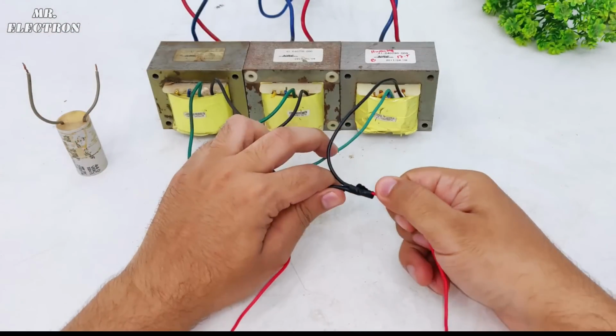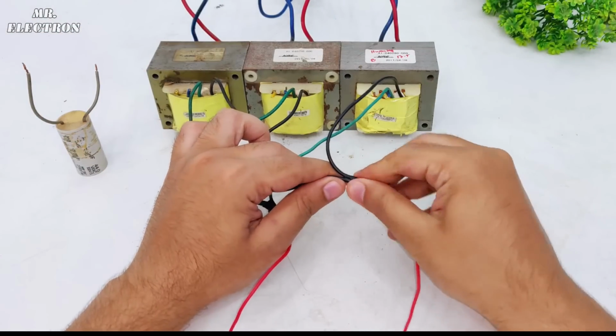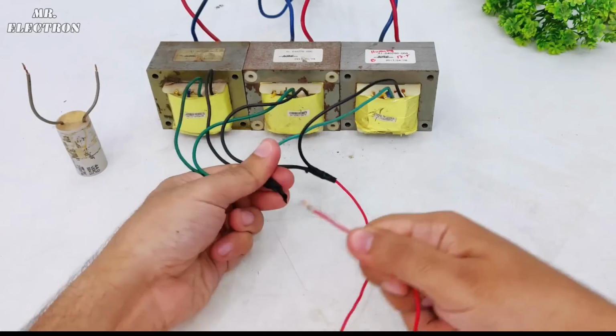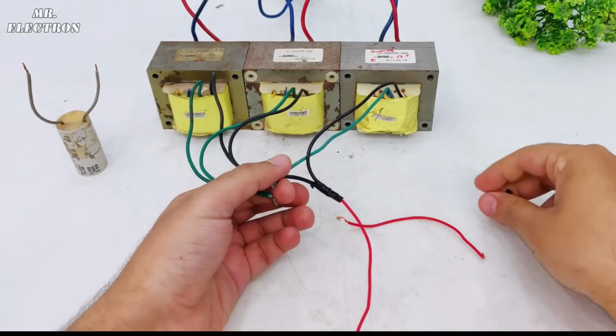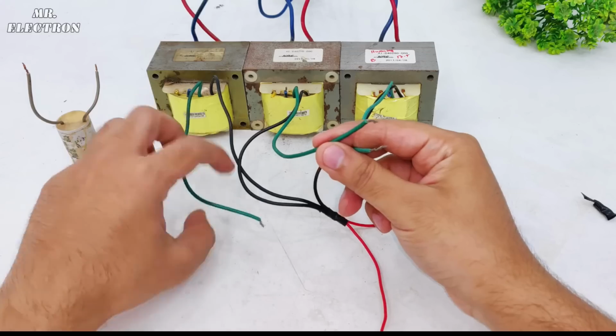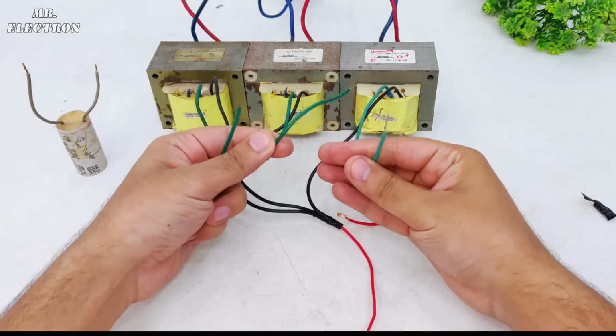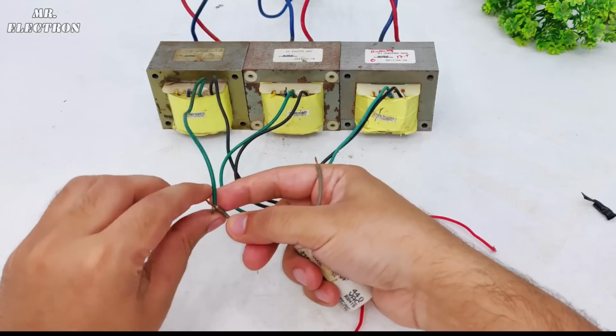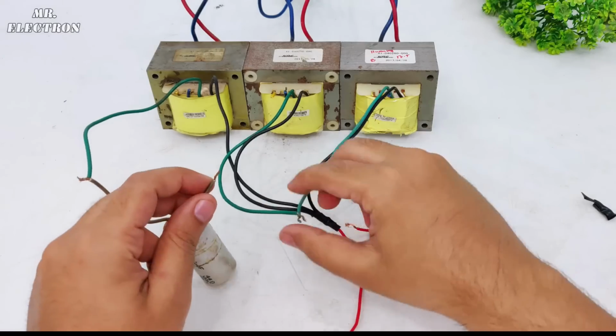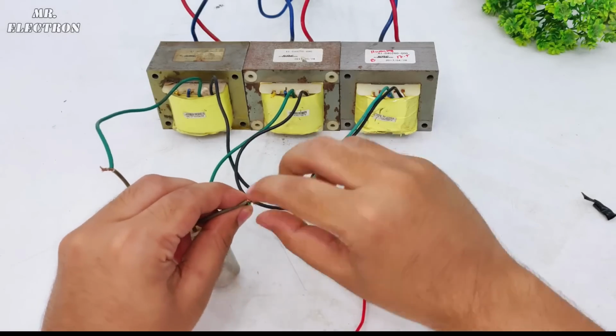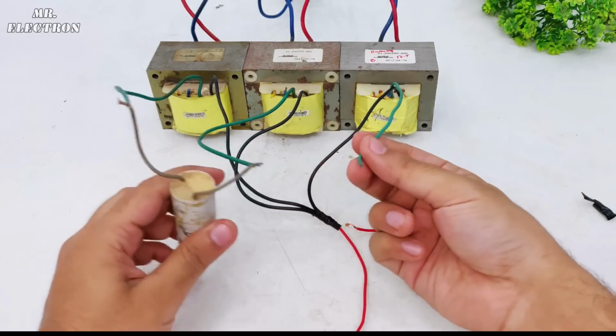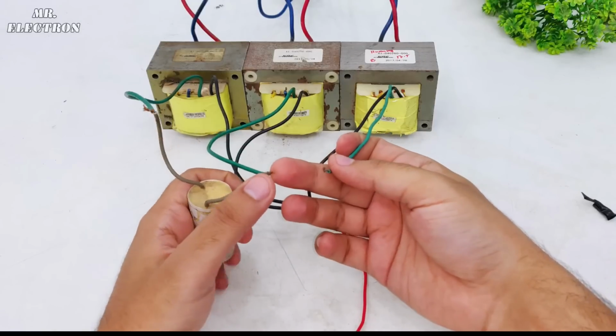I'm going to start with the star connection. This looks tight, this one is loose. So we are going to have this black as the common point, and these green ones are going to be the three-phase input wires. For the capacitor, let's choose two of the transformers and connect the green wires like this, and these two points are going to be connected to the 220 volt supply.